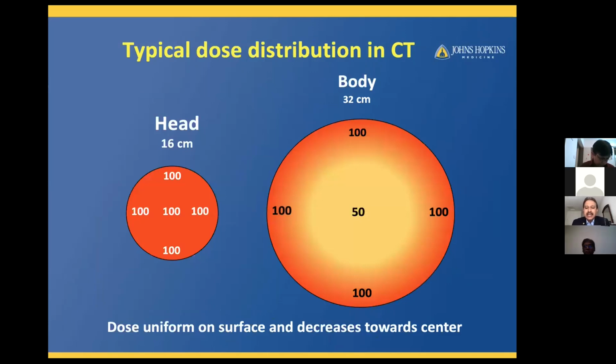Typical dose distribution in CT varies by the size of the object. If the object is small, the surface dose is almost the same as the center dose. If the object is large, such as a body phantom or the abdominal area of a patient, the center dose is almost half of the surface dose. This understanding is very important when we are doing dosimetry, because we can't simply measure dose on the surface while ignoring the dose at the center. In radiography or fluoroscopy, the surface dose is the highest and then it decreases. Whereas here, the surface dose is uniform as we are acquiring the data around the patient, and it's half at the center.